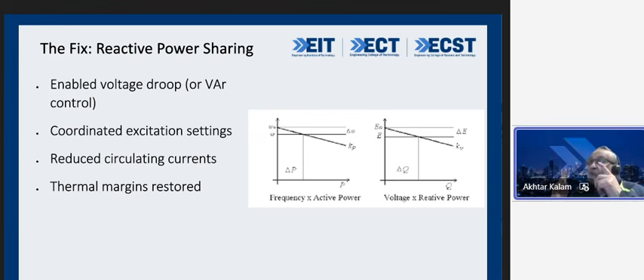You have to enable voltage droop or VAR control. You have to have coordinated excitation settings. You have to reduce the circulating current - remember the silent killer? And you have to restore the thermal rating or the margins. You will find the reactive component which we have neglected is as critical for long-term reliability, so you cannot ignore it.